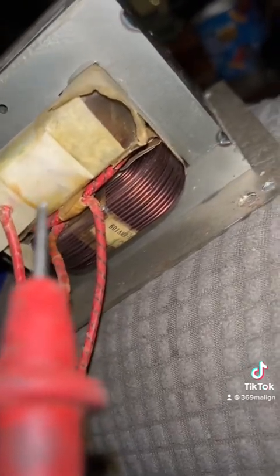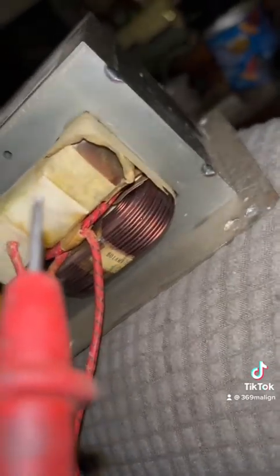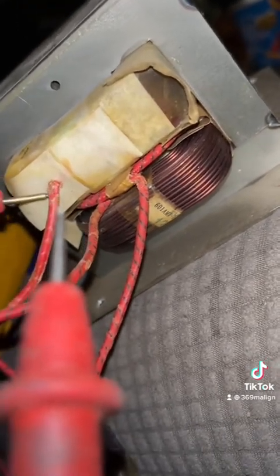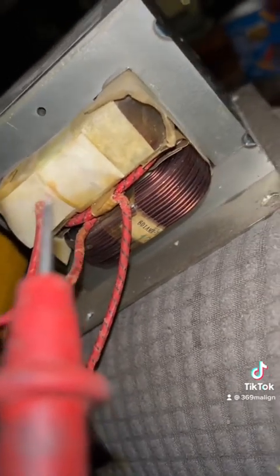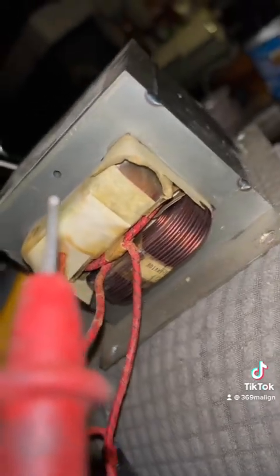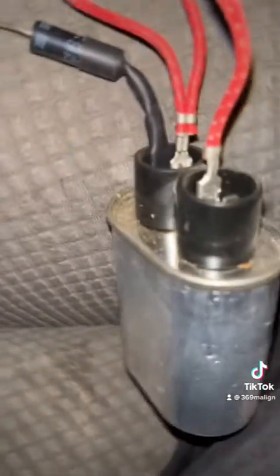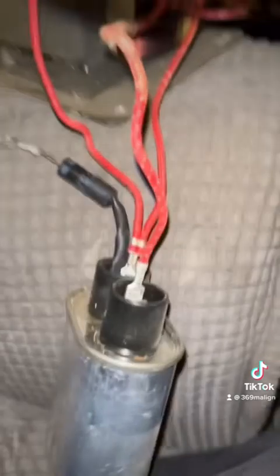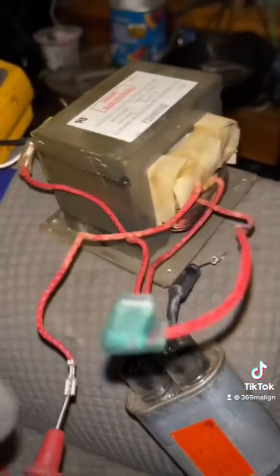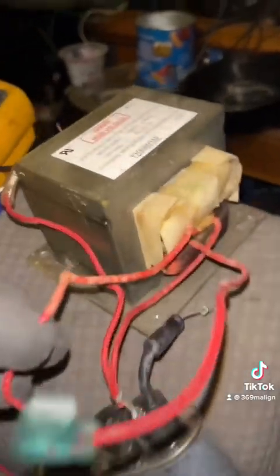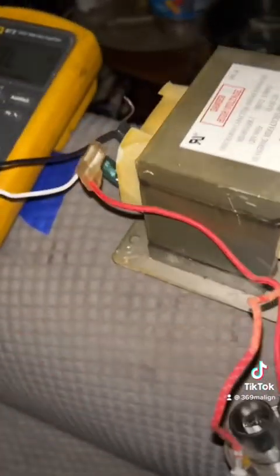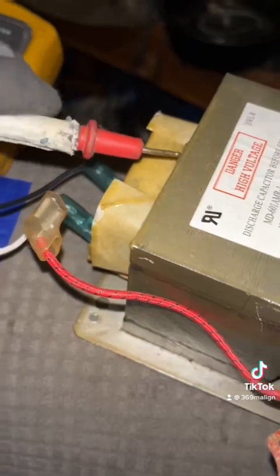What we're going to do is use only the hot wire here, the one coming directly from the coil, and the other one that's actually attached to the frame. So we have to disconnect it from the capacitor to check this. I have one lead attached to the one coming out of the center of the coil in the back, and I go to the frame.